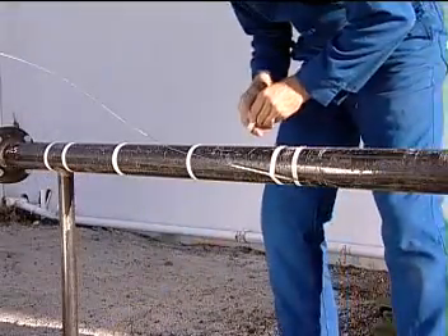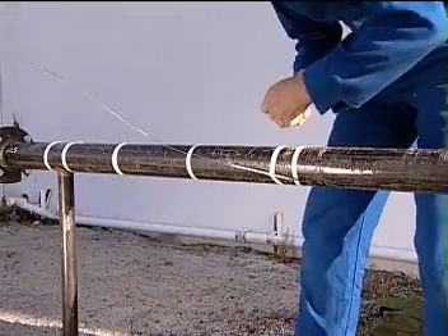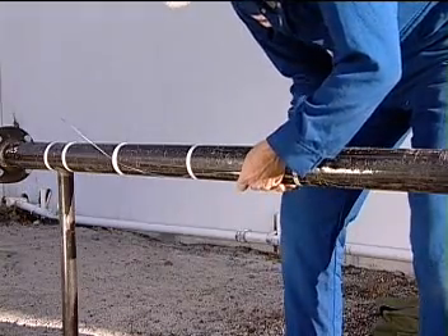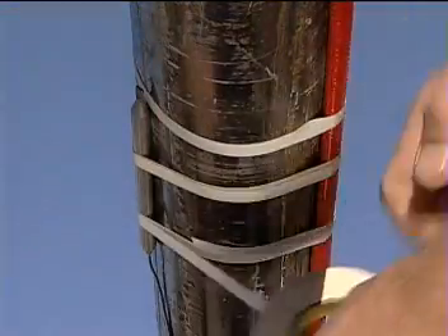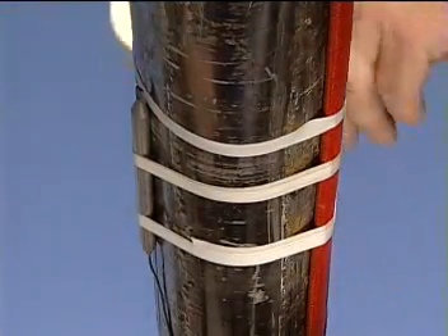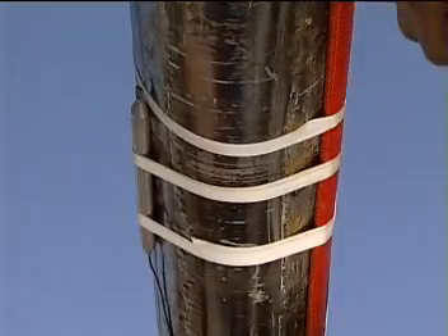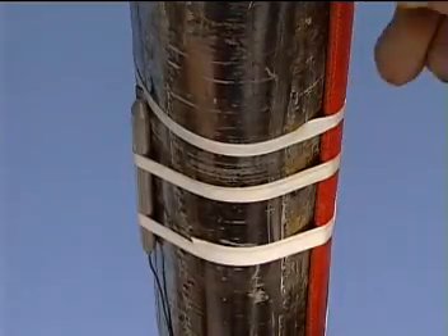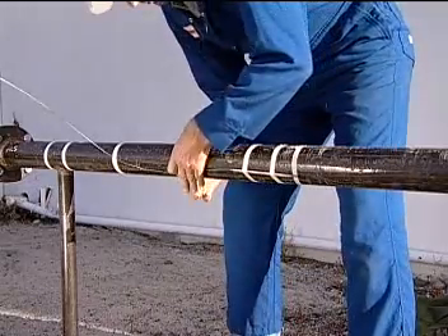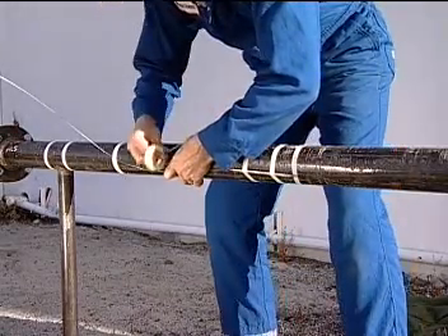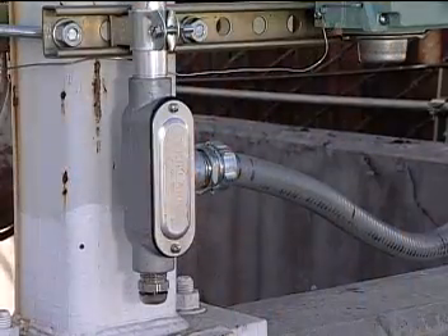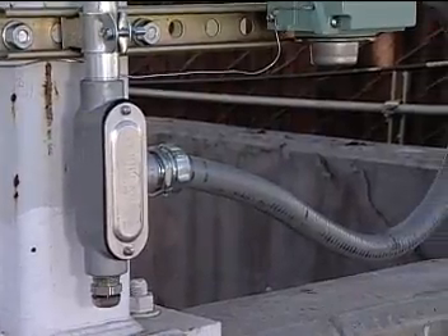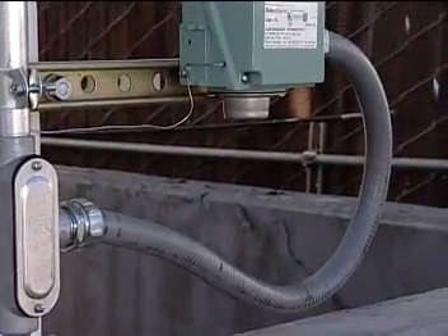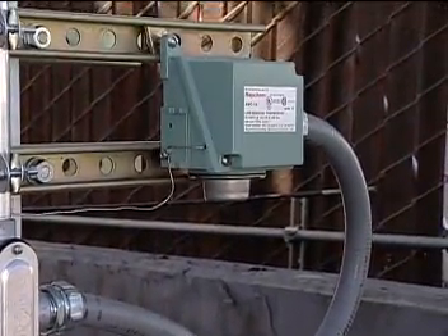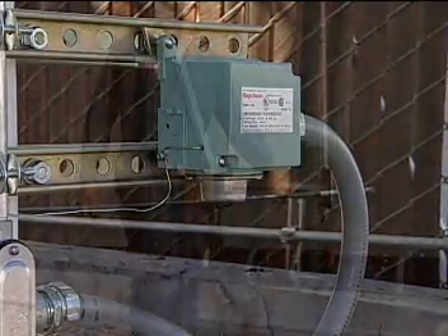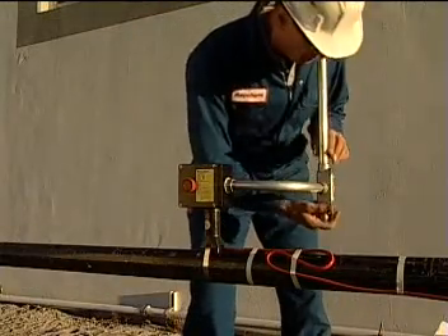A line-sensing thermostat is used to monitor the temperature of the pipe on which the heat tracing is mounted. The bulb of the thermostat should be mounted on the bottom part of the pipe, 90 degrees from the heater and at least 3 feet from the nearest heat sink. Tape the bulb firmly to the pipe, ensuring good contact. Also, make sure that the thermostat is mounted so that condensation from the connecting conduit will not drain into the enclosure. Next, visually inspect the system for damage.